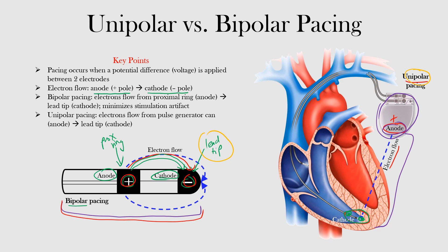Let's review what we discussed. Pacing occurs when there's a potential difference — a voltage — applied between two electrodes. Electron flow is always from the anode, the positive end, to the cathode, the negative pole. With bipolar pacing, electrons go from the proximal ring (anode) to the lead tip (cathode), and this is the configuration that minimizes the stimulation artifact on the EKG.